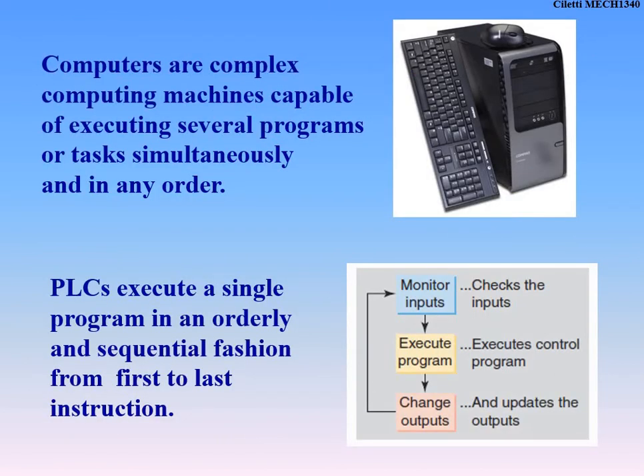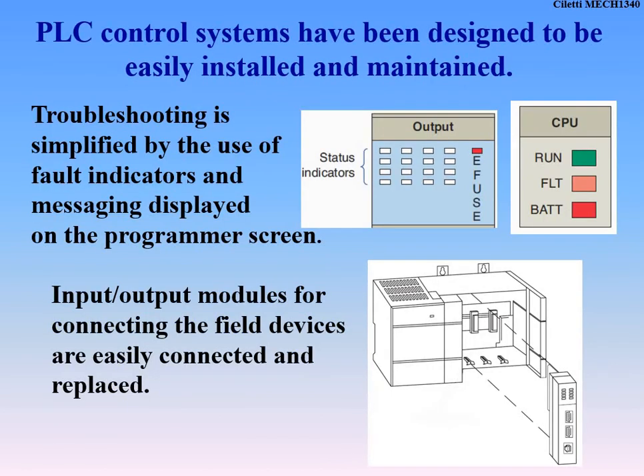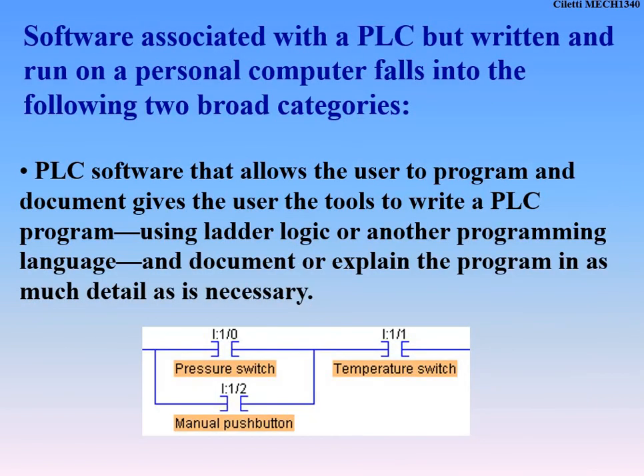Computers are much more complex, and there's always the Windows issue — Windows updating, all those other things that slow you down. There is nothing to slow down a PLC. It does every single thing in an orderly fashion — scanning the inputs, executing the program, updating the outputs, over and over. It always reads from left to right, top to bottom. Your PLC will tell you if everything is running and good, or if there's a fault. We can monitor the program and check which input or output is causing the fault or why the PLC can't start up.